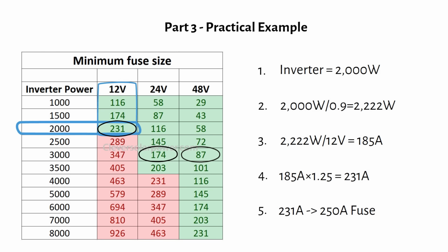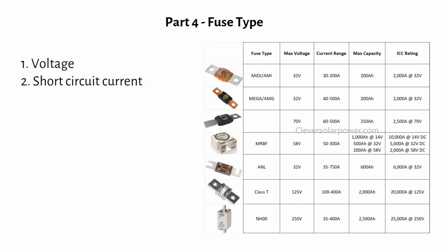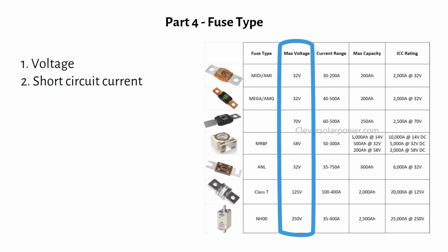Okay, now that we know the fuse size you need, we have to pick the right type of fuse. We do this by checking the voltage rating and the short circuit current rating. First thing to check is the voltage rating. I have created a table that you can screenshot showing the different types of fuses that can be used for different scenarios. Every fuse has a maximum voltage. If you go past that voltage, that fuse might not actually disconnect the circuit. It can arc and keep conducting. So if your fuse says 32 volts max, that fuse is not allowed on a 48 volt system.